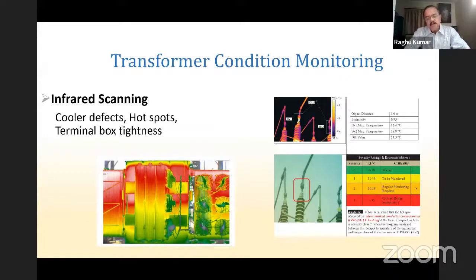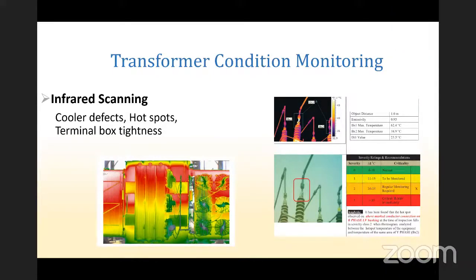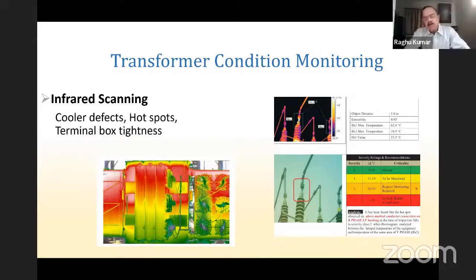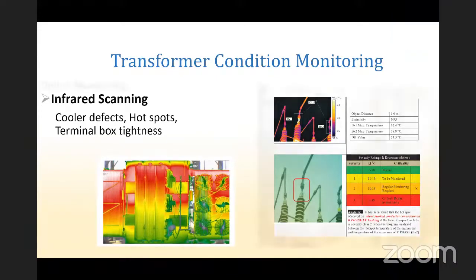And if it is between 20 to 35 degrees, then the monitoring frequency is increased. If it is greater than 35 degrees, immediate action is required, and shutdown is arranged and checked. Most of the time, it has been found that a loose connection was the reason for the overheating. So this is how infrared scanning cases are.